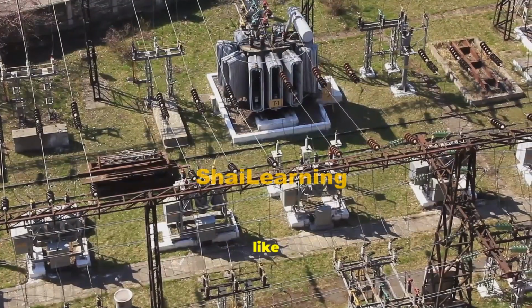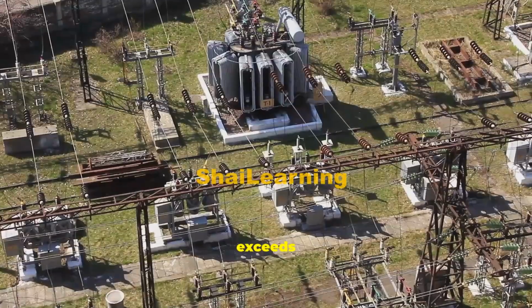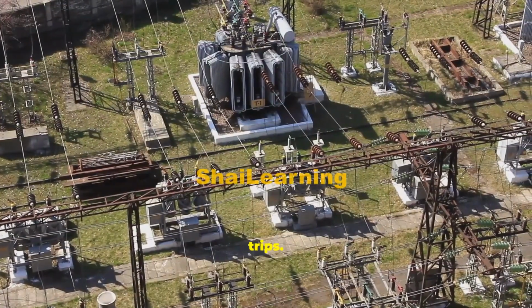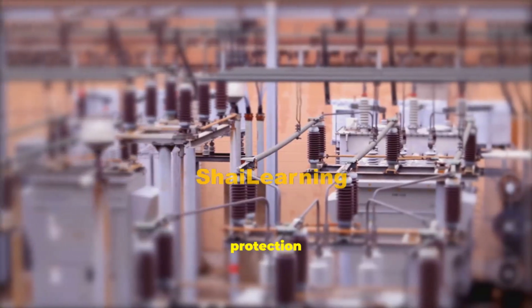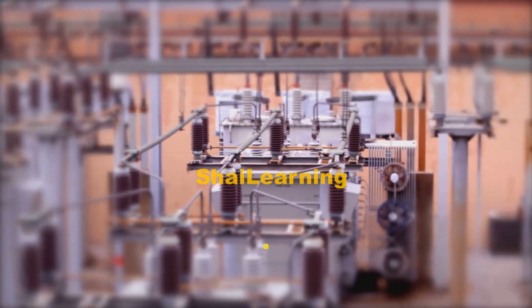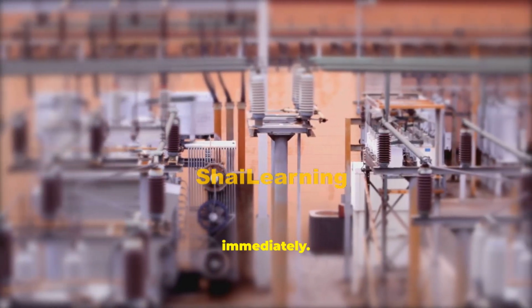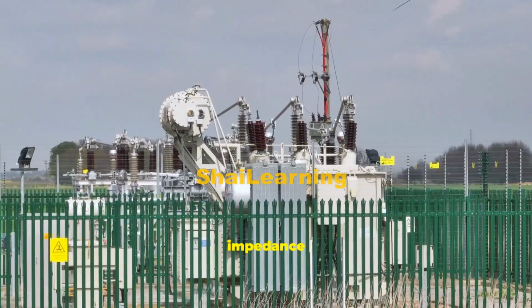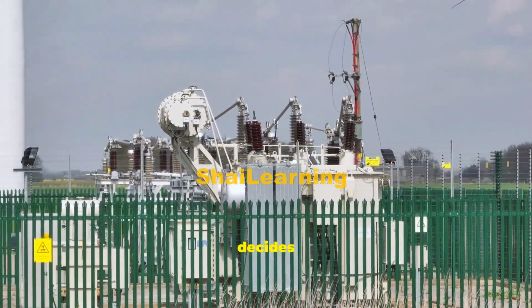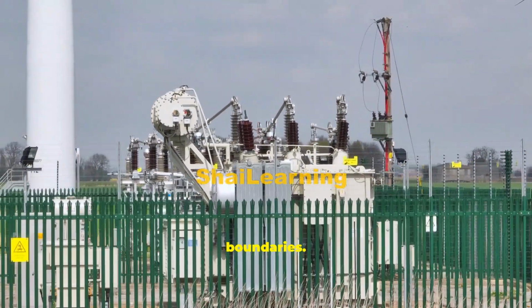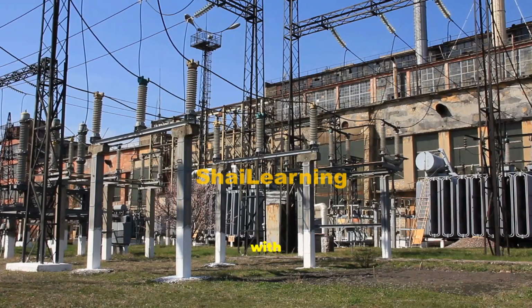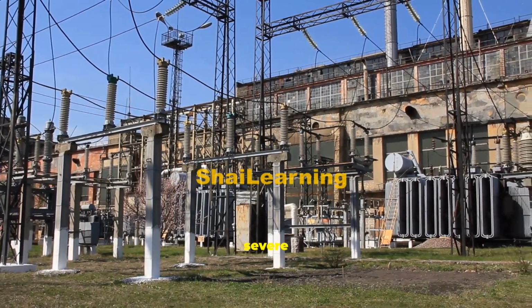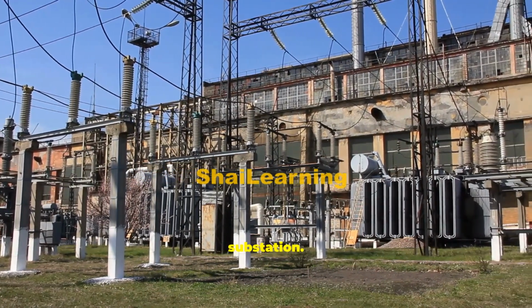Overcurrent protection works like your home breaker. If current exceeds a set limit for a time, it trips. Differential protection compares current in and out. A mismatch signals an internal fault and trips immediately. Distance protection calculates impedance to estimate fault distance and decides within zone boundaries. Bus protection must operate with extreme speed for one of the most severe events in a substation.